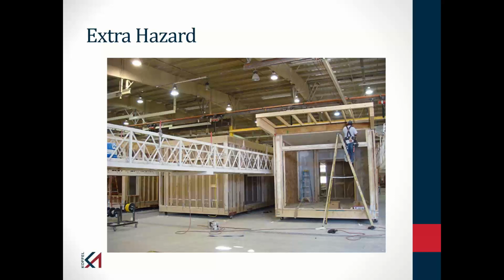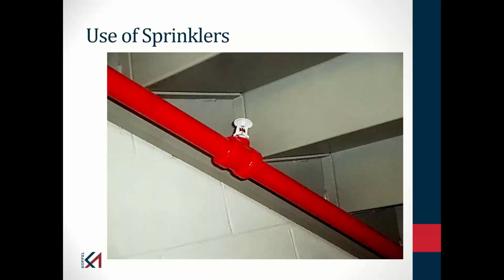I'm not going to go through storage. There's a whole different way we deal with storage, and it's called commodity classifications. And it's based upon the commodity that's being stored, how combustible that commodity is. So with storage, if I take that example and somebody says, well, I want to take this office and convert it to a storage room, we now need to go look at storage requirements for that space. And we define something called a miscellaneous storage occupancy, something that's incidental to the primary use of the building, like maybe that small office might be, that would be miscellaneous storage. We have to evaluate whether the current sprinkler design and spacing is adequate for that new use, that new hazard. We'll talk a little bit more about that when we get to NFPA 25.